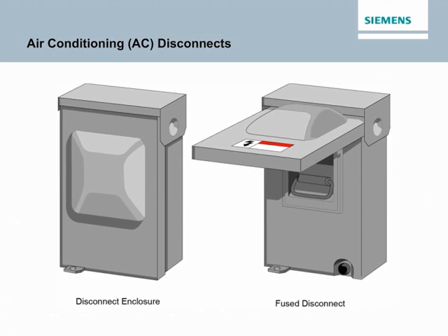The fused pullouts are 240-volt, 2-pole, 30 or 60 amps. The non-fused pullouts are 240-volt, 2-pole, 60 amps. The molded case switch disconnects are 240-volt, 2-pole, 50 or 60 amps. Molded case switch disconnects are supplied with non-automatic QP molded case switch circuit breakers.